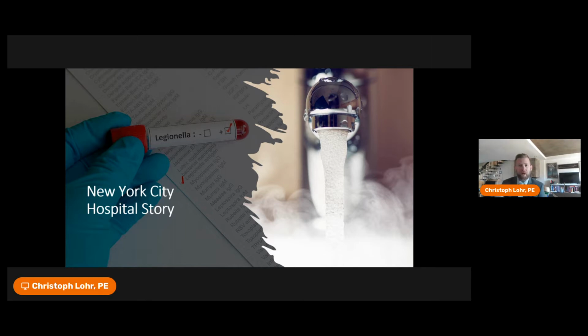And the hospital, they had a water management program. They had supplemental disinfection. And within a few weeks of the hospital opening, they had Legionella positivity in their facility. In terms of the hot water system was testing positive. Fortunately, they didn't have any cases, but they were really struggling to try to figure out what the cause was.